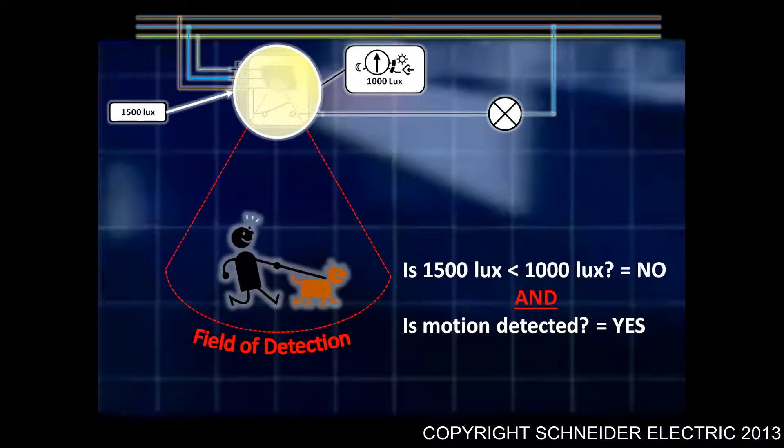Is the ambient light less than 1000 lux? In this particular case, it's actually greater, so we say no. And is motion being detected? Yes. In this particular case, what happens is nothing. The sensor has detected that there is sufficient light within that area and it's not going to turn on that light. So the light remains off.